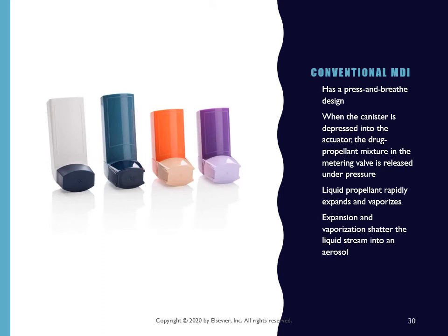Let's talk first about conventional MDIs. It has a press and breathe design. When the canister is depressed into the actuator, the drug propellant mixture in the metering valve is released under pressure. The liquid propellant rapidly expands and vaporizes. The expansion and vaporization shatter the liquid stream into aerosol particles, and those are inhaled by the patient.